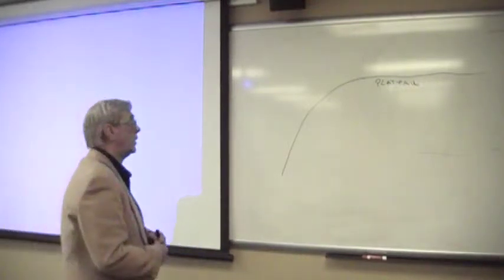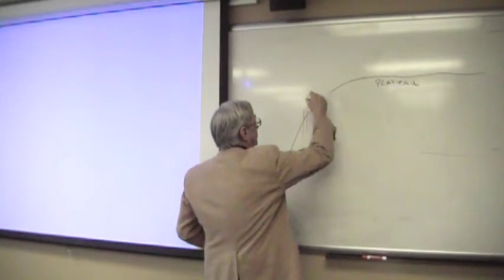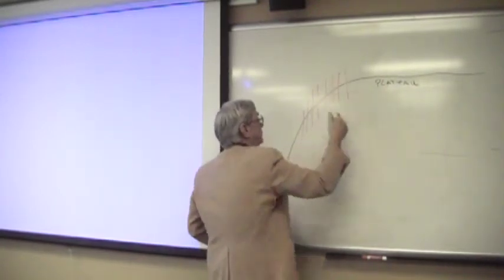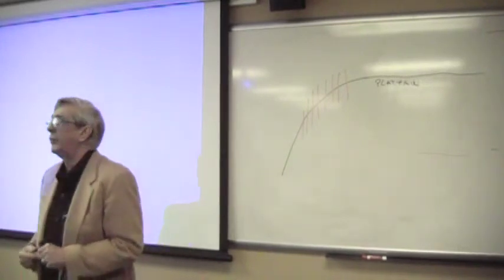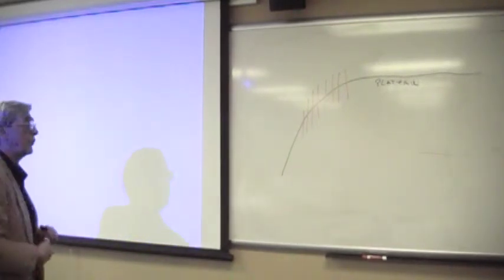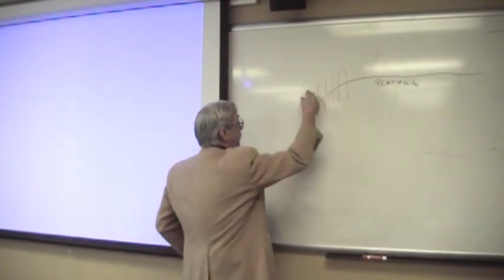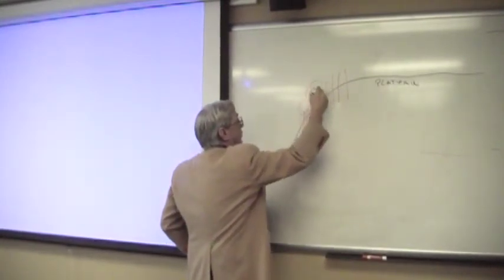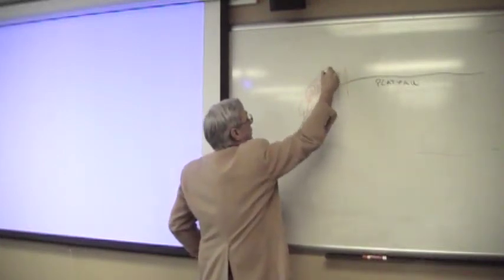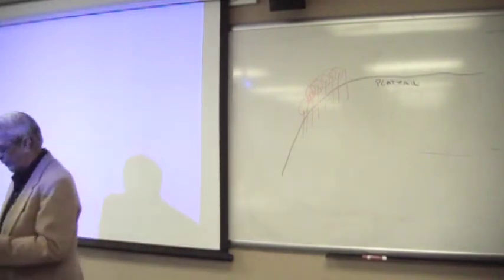An invalid sample is triggered when, as this reading is going up, you have a lot of individual readings. The computer, as this thing is moving up, is watching these and it's actually averaging every two of these readings. It compares the current average with the last average. No two of these averages should be going down consecutively. If they do, it's going to trigger an invalid sample.